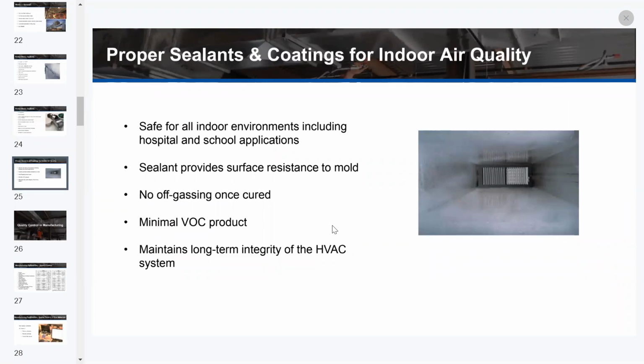So indoor air quality is especially important in such venues as hospitals and schools, where compromised people and children are at risk of being exposed to harmful bacteria and viruses. In hospitals and schools, sealants should provide a surface that is resistant to mold and bacteria growth. They should have no off-gassing once cured and minimal VOC content when in the liquid state. Sealants that are flexible and can move with the duct system give long-term integrity of the HVAC duct system. So you need to look for sealants and mastics, both water-based and solvent-based, that are below the LEED limit, qualify for LEED credit contribution, and are under the requirements for the South Coast Air Quality Management District.